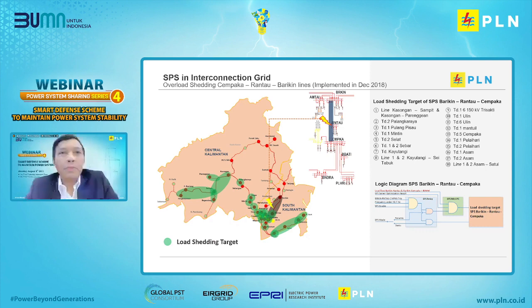This is the fourth SPS in Kalimantan, different from the previous slide. We have a different approach to keep the generator operating and avoid overspeed in Bangkanai Power Plant. The Tanjung Buntok Teweh line is a radial network for the supply of Bangkanai Power Plant, while the load in that area is only 20 to 30 megawatt. So, if one of the sections trips two lines, Bangkanai Power Plant will survive with only 20 to 30 megawatt. The scheme prepared is an engine trip by leaving 3 to 5 engines from 16 engines. And at the same time, we open one transmission line to ensure voltage security.